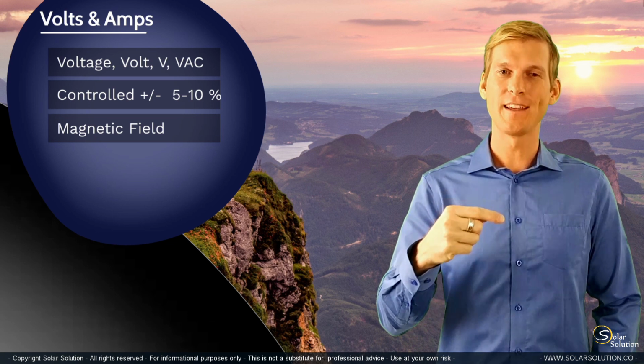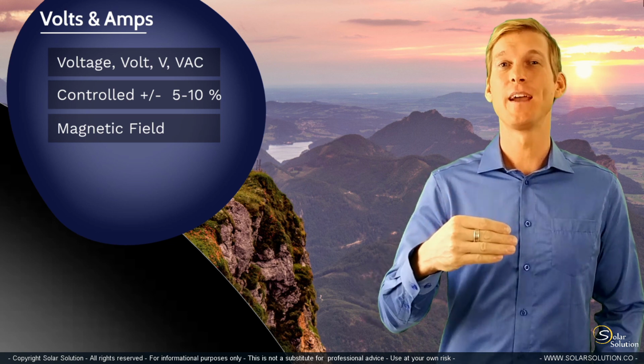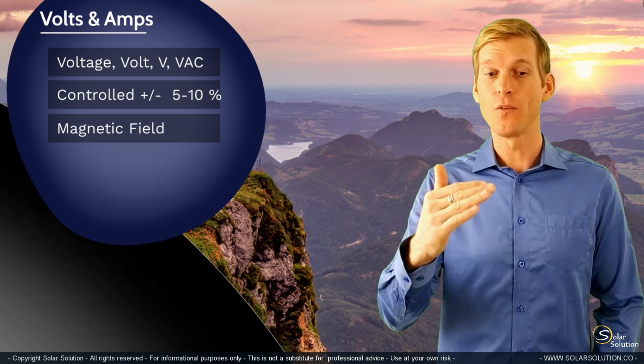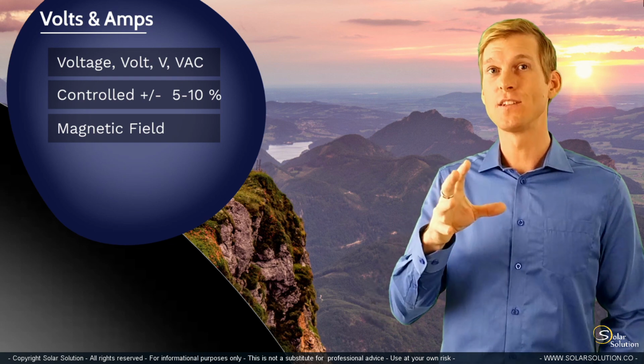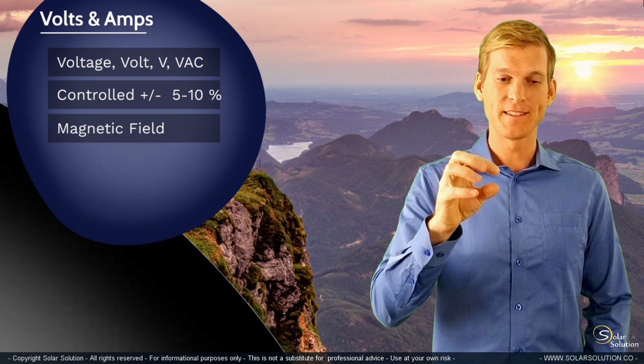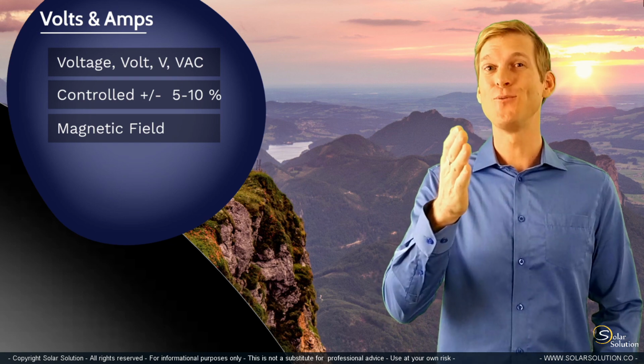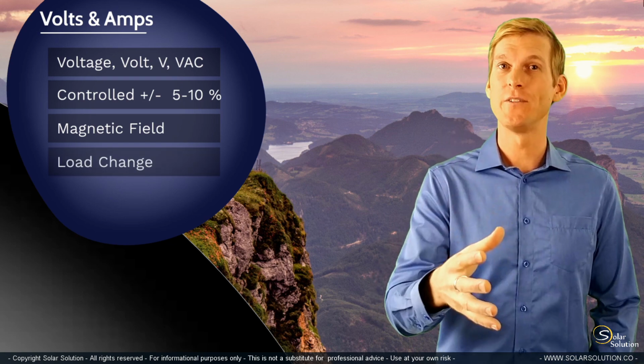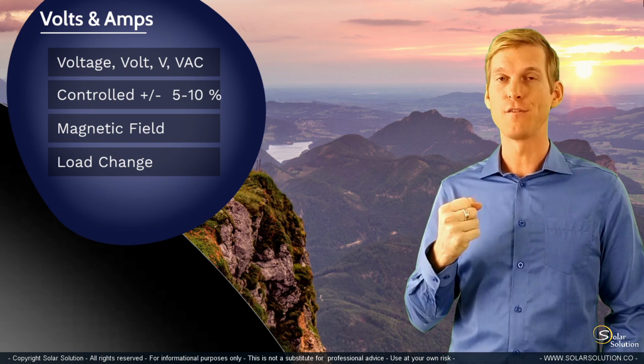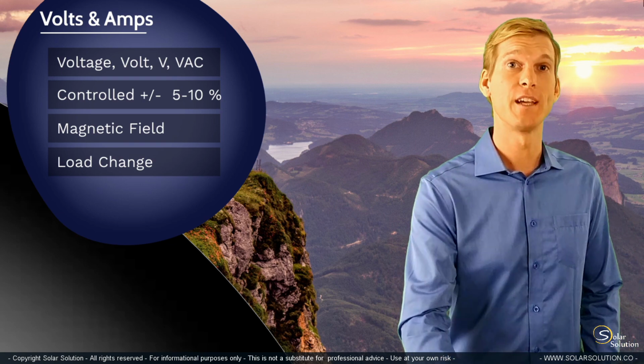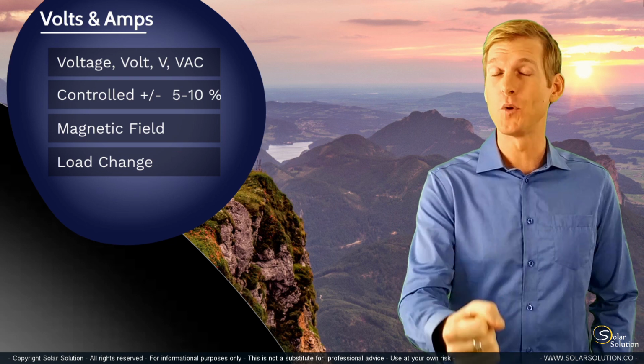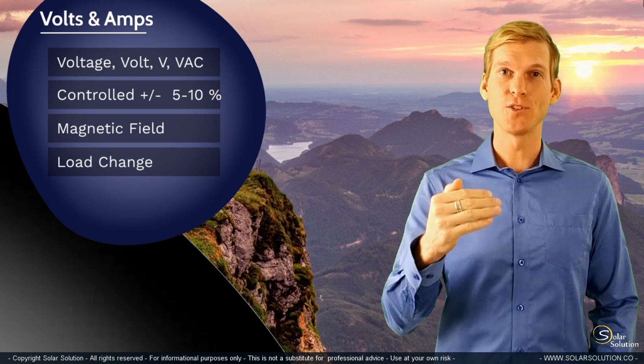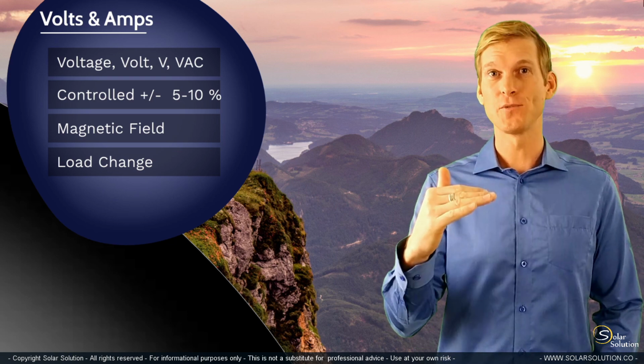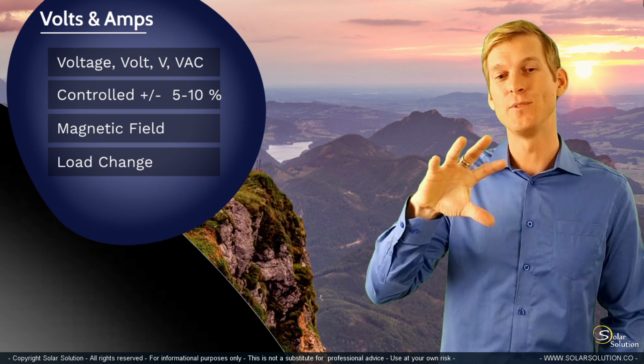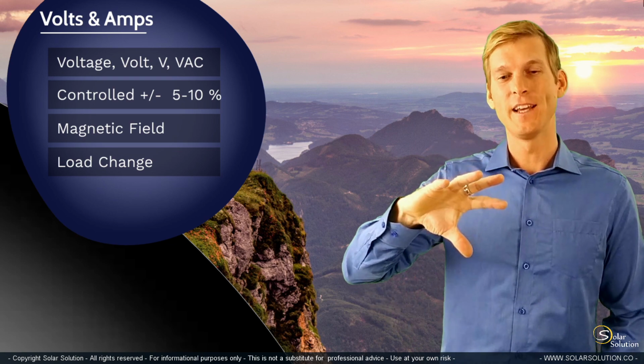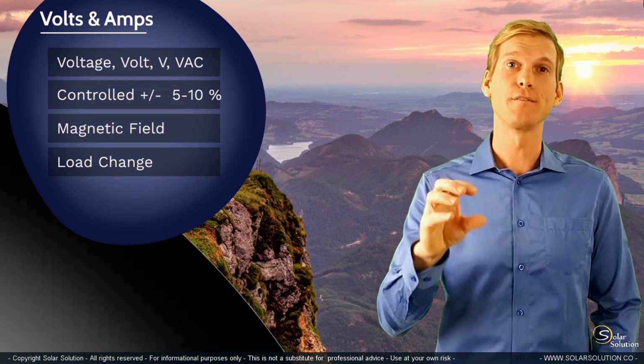But it's important to realize that the real reason behind why your voltage is fluctuating and why the generator needs to adjust the magnetic field strength is basically because of you. Because if you are changing the loads on a generator, if you are reducing the amount of power that you're taking from it, or all of a sudden you're asking more power from the generator, then the result is that the voltage starts to fluctuate, and therefore the generator tries to mitigate this by adjusting the field strength of the magnetic field inside.